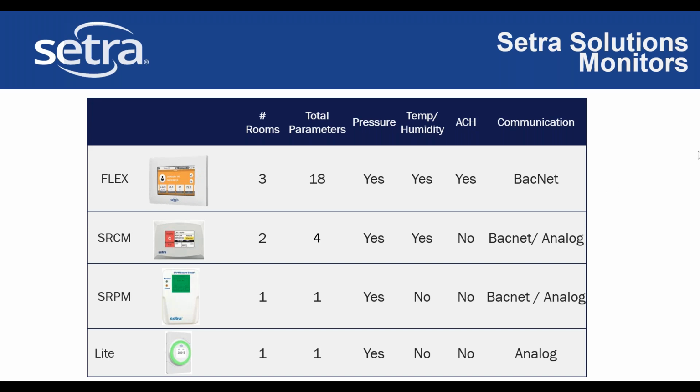A question by Mr. Hamza Saleem. For the Setra solutions monitors being offered, would the communication be over TCP/IP or RS-485? So that slightly depends upon the monitor. The Flex monitor can do all of those options. The SRCM monitor can. Can you remember? I just blanked on the IP. The SRCM and the SRPM, they do the RS-485, right? MSTP, so BACnet over MSTP. The Flex has the IP option. Yeah, that was perfect. The Lite is analog only at this time.